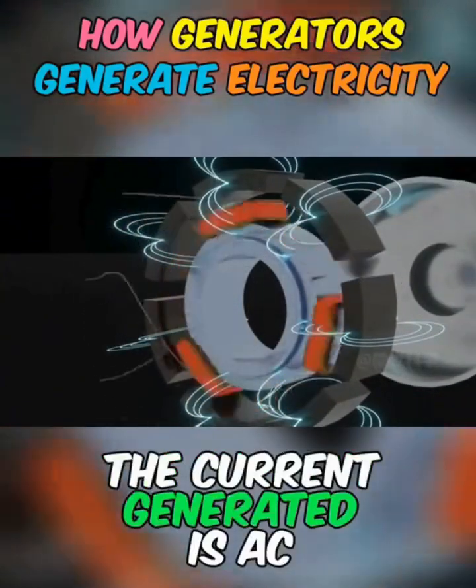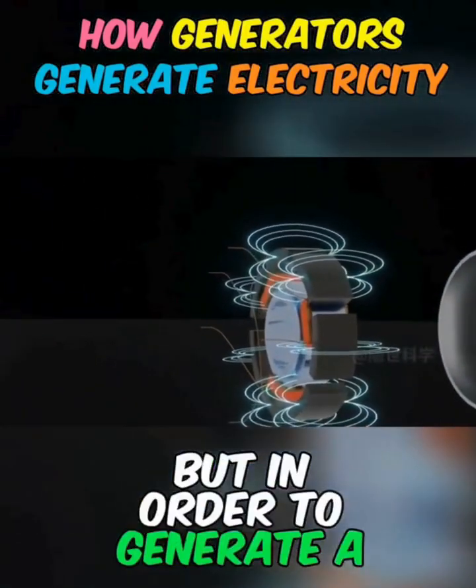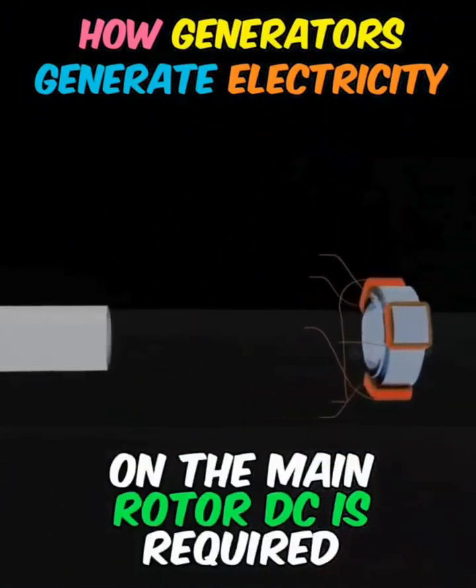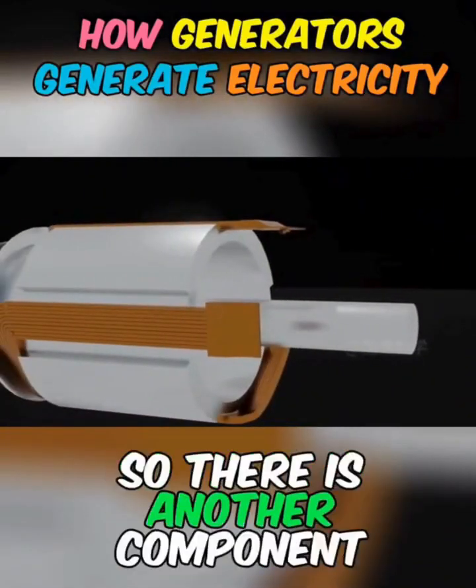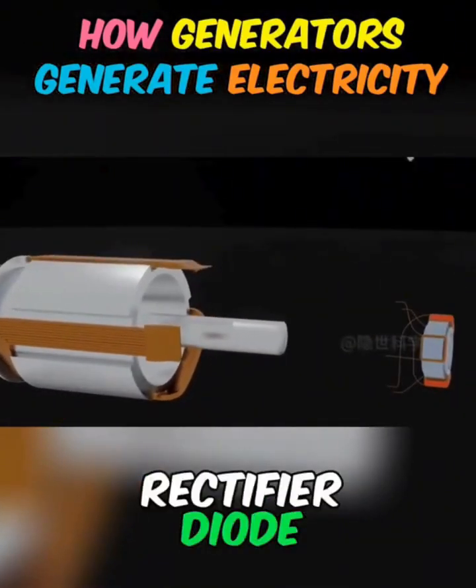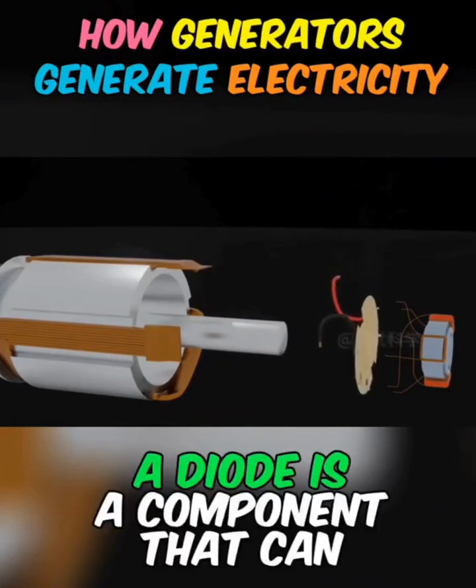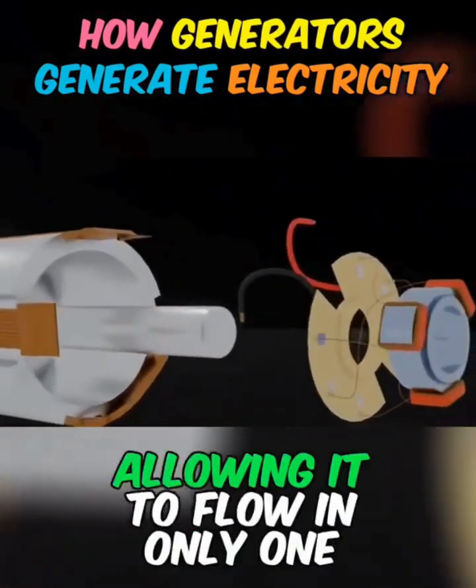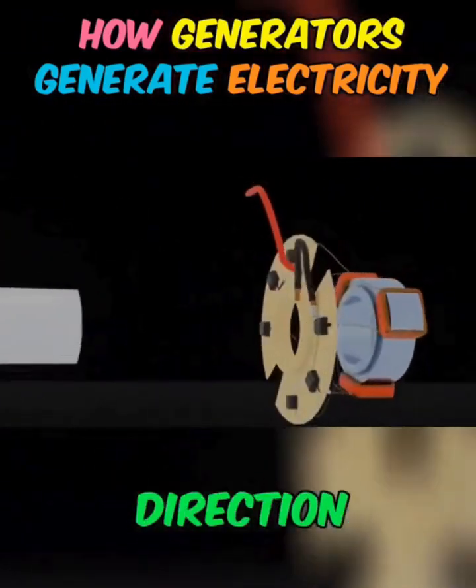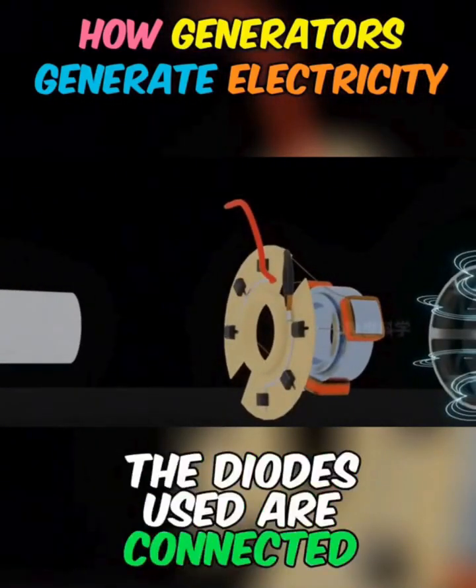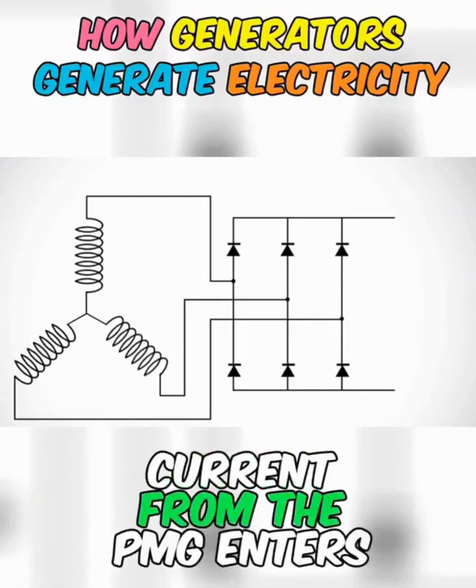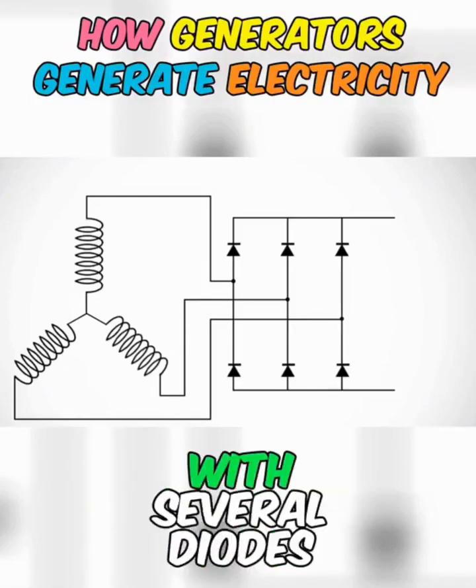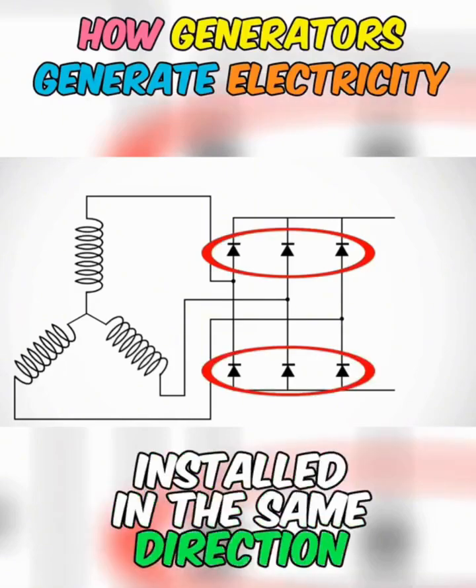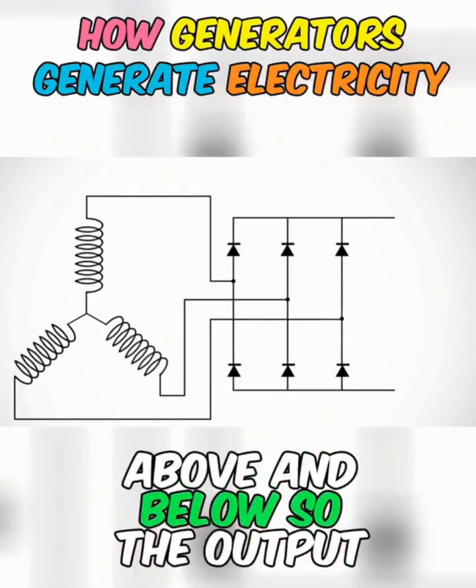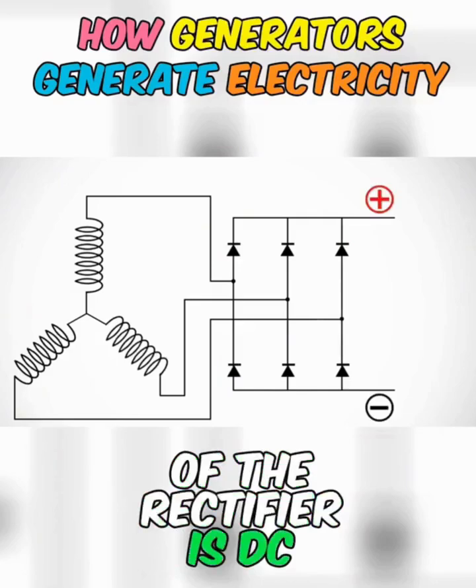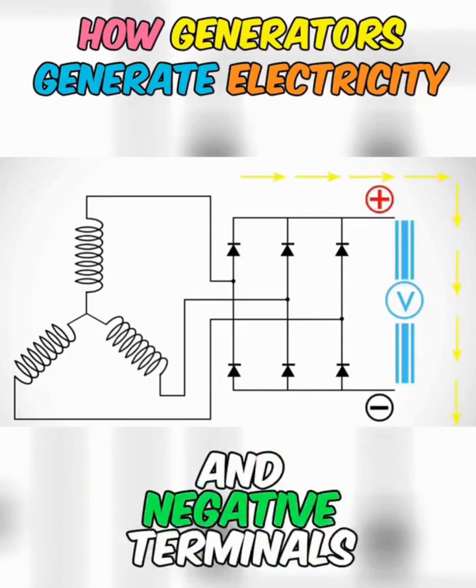The current generated is AC, but in order to generate a magnetic field on the main rotor, DC is required. So there is another component: rectifier diode. A diode is a component that can rectify current, allowing it to flow in only one direction. The diodes used are connected in the following way. Current from the PMG enters from the middle, with several diodes installed in the same direction above and below. So the output of the rectifier is DC transmitted through the positive and negative terminals.